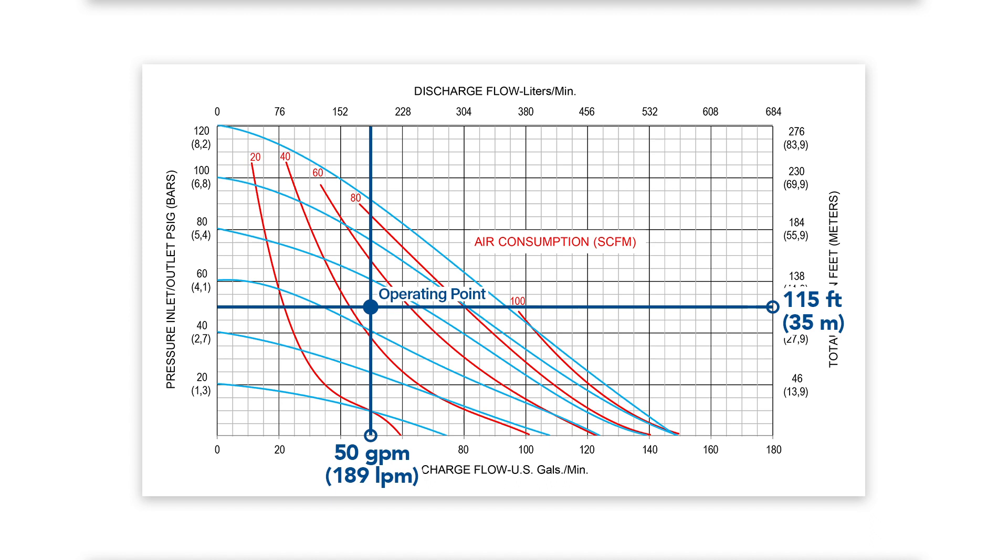From this operating point, the performance curve identifies the AODD pump's air consumption by following the red curve axis. In this example, by following the red curve axis, which lies between 40 and 60 SCFM, you can expect the AODD pump's air consumption to be about 48 SCFM.